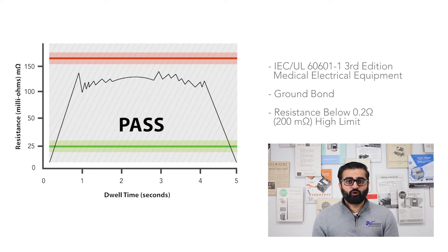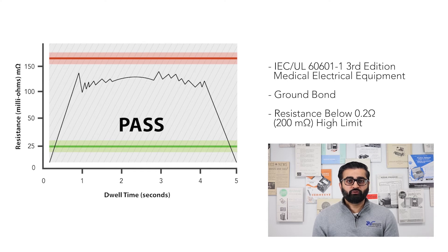Next, let's take a look at limits for ground bond tests. IEC 60601 requires that the resistance of ground circuit be below 200 milliohms. This gives us our high limit for ground bond tests. In order to pass the ground bond test, the resistance has to be under 200 milliohms.